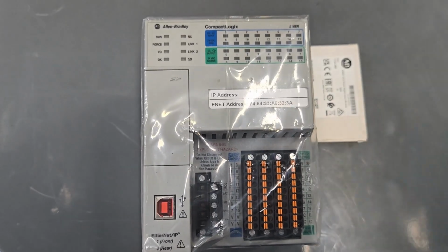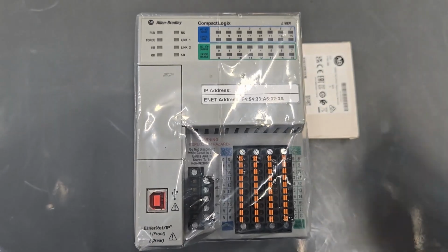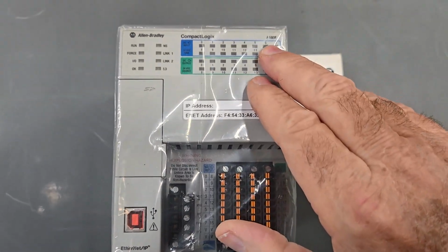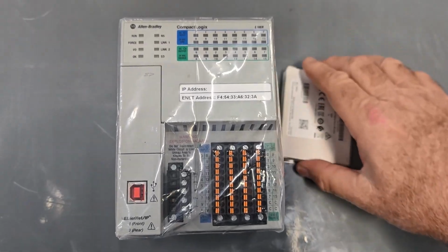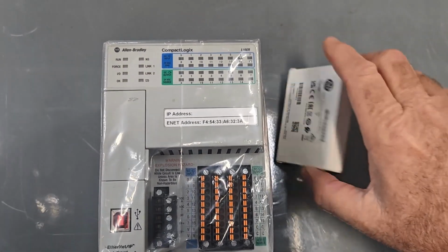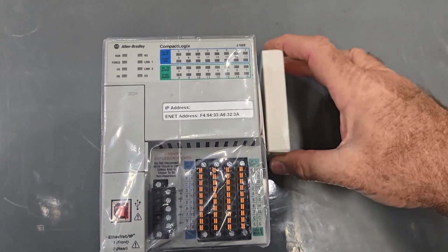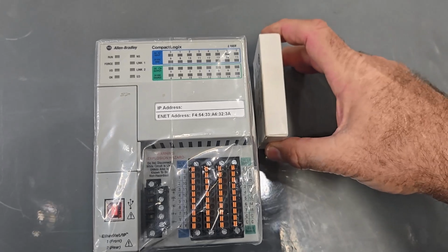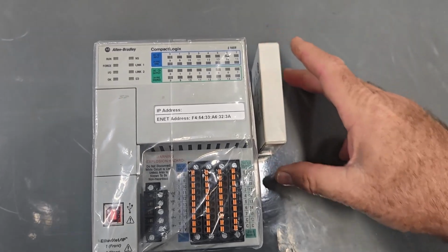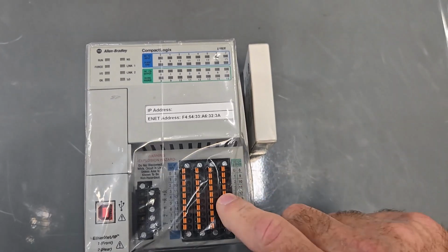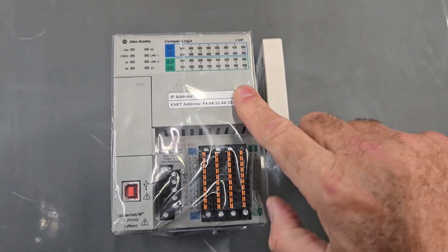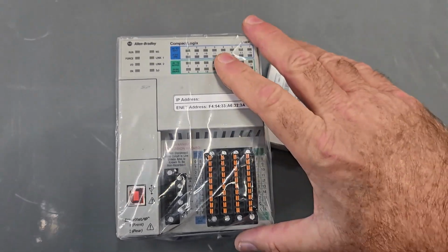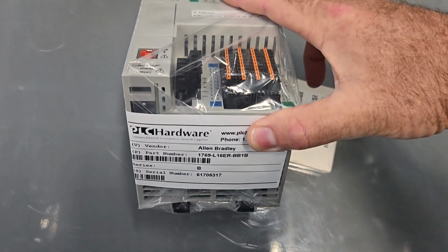Yeah, we're going to replace that MicroLogix 1000 with an L16ER. That's the plan. This doesn't have enough inputs, so we're going to have an auxiliary input block, which is going to sit on a carrier with connector blocks for the wires coming in. So we're going to upgrade to this, and this has a lot of functions that the other doesn't, including Ethernet connectivity.